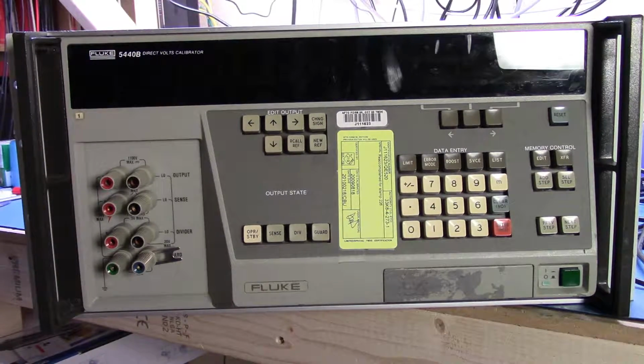I wanted a known starting point, so I sent my 5440B/AF off to Fluke, and they noticed it had a little bit of problems, so they've been letting it run for a while. It seems to have come good, but there was an issue with the relays on the 1000 volt, or 1100 volt, range, and they were thinking they might have to replace the relays.